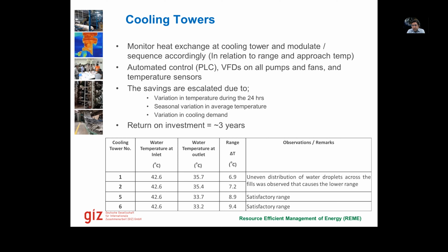So for example, sometimes there's one compressor running, sometimes there are 2 compressors running, sometimes the compressors are on load, sometimes they're off load. So the cooling demand varies. If we have an automated system with VFDs installed on pumps and fans, we can typically get a return on investment in less than 3 years. If we have a bigger system, the payback is quicker.